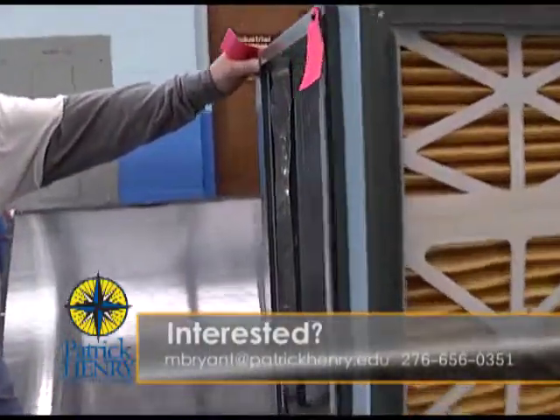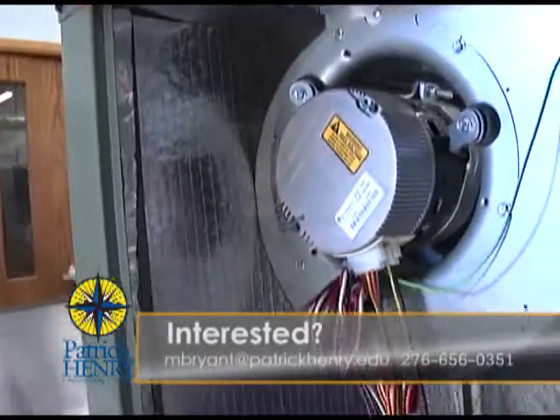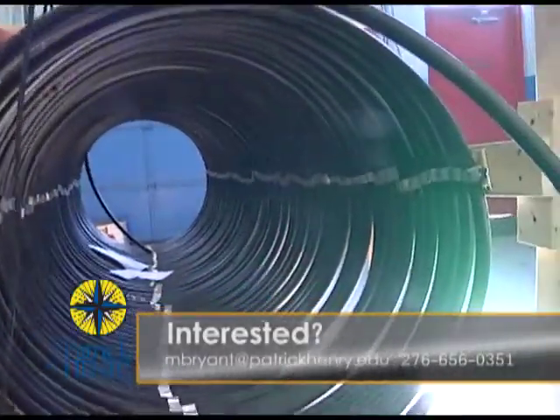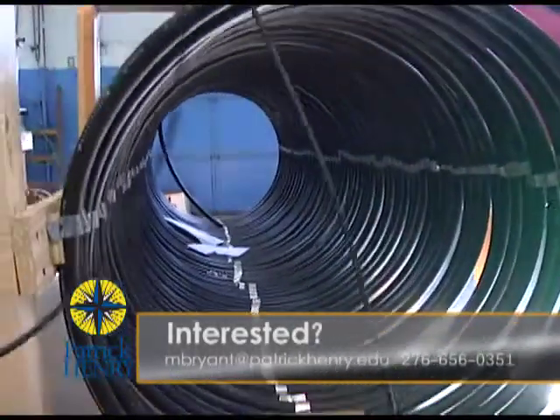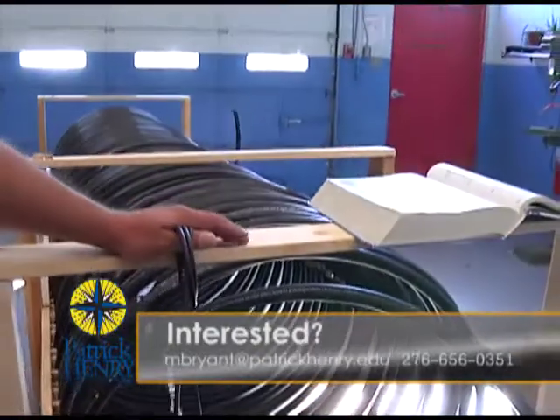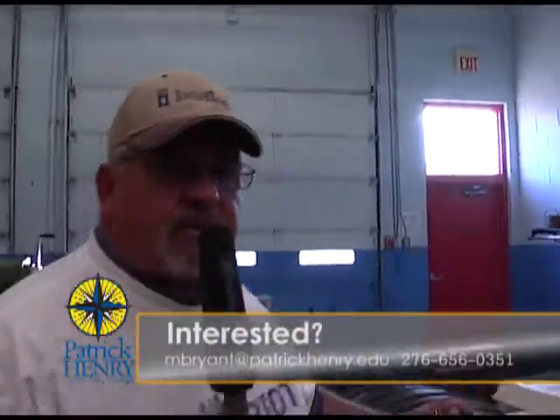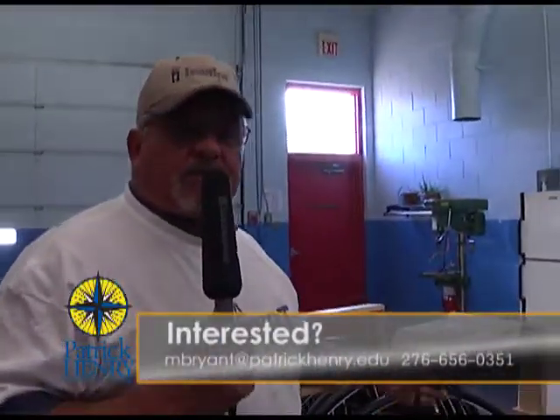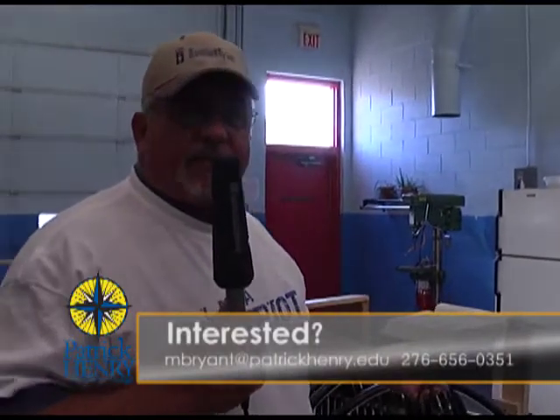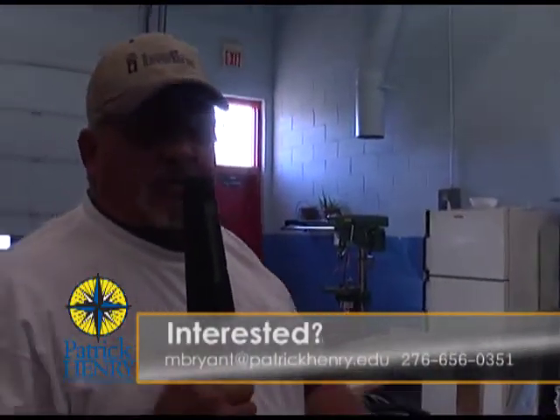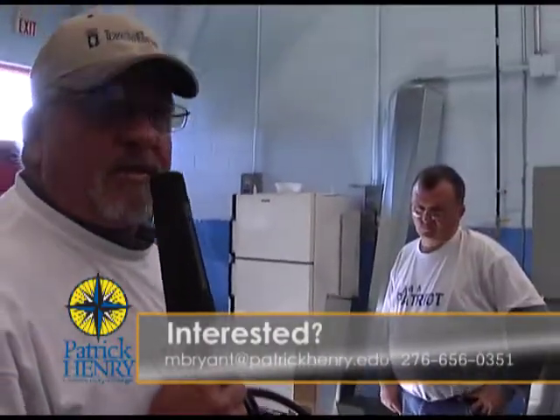With this, we're using geothermal for the outside. The coil section here is buried in the ground. It absorbs heat in the ground because the Earth's temperature is different. You can actually cool in the summertime using the Earth's temperatures, because the temperature of the ground is 60-some degrees or below. So we can pull the heat, extracting it from there, bring it in, and circulate it through our system here.